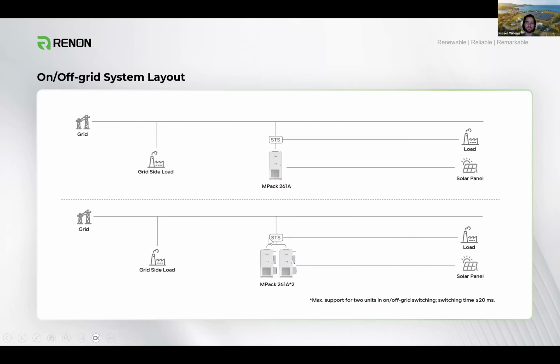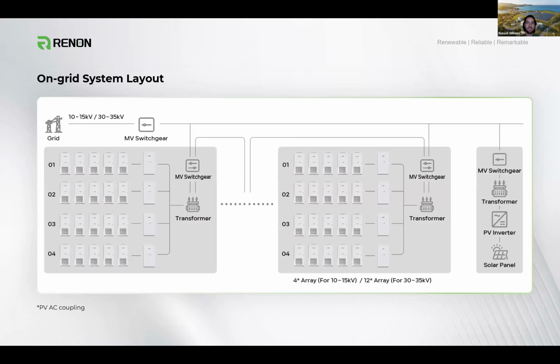When we have that STS operating, the switching time is less than 20 milliseconds, so really rapid changeover time. That tends to meet the threshold for critical computing applications. Some smaller UPSs are still needed on a server-by-server basis if there's a requirement of 5 milliseconds or less, so there's some flexibility there. But in terms of human experience in an operating room or a facility like a hospital, as I mentioned, they're not going to see the lights flicker. It's a really rapid changeover, a true STS, which I think is a rare opportunity to find integrated into the equipment these days.